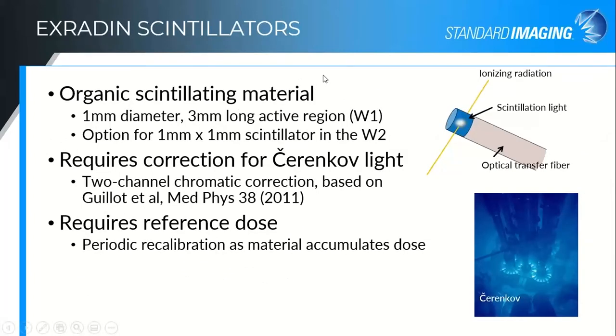So what are scintillators really? It's an organic scintillating material — depending on which detector you have, it's either a one millimeter diameter, three millimeter long, or a one millimeter diameter, one millimeter long active scintillating region. That scintillating material is coupled to an optical transfer fiber that is PMMA — water equivalent at these energies, at least close enough that it's not affecting your measurements. The scintillator itself also matters and it is water equivalent as well.